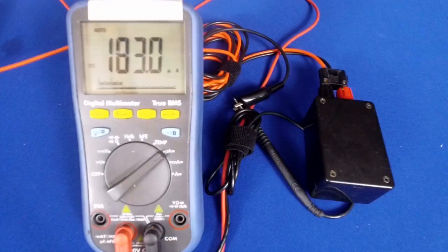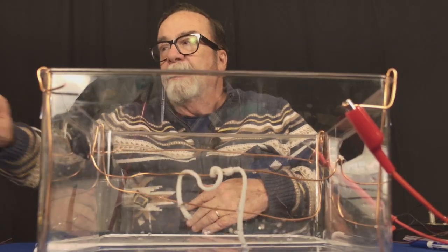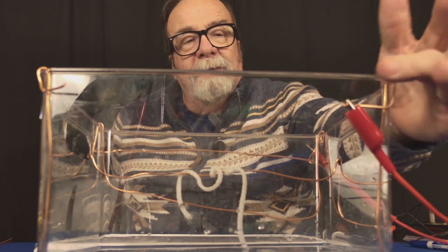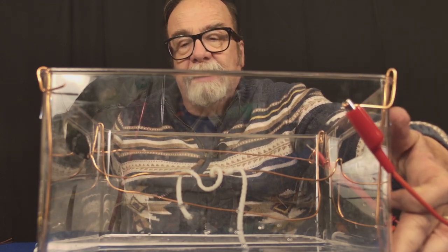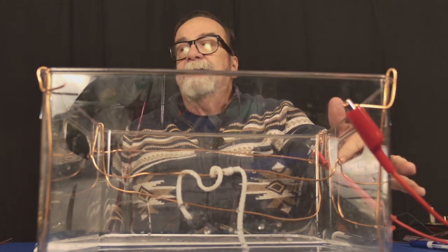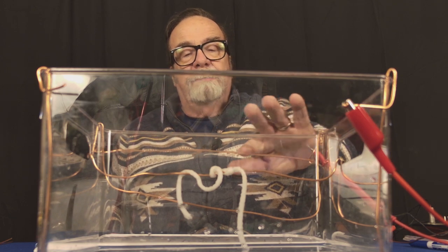is basically, here's my meter, and here's this little black box. Well, this little black box is a 24 volt, power limited to 100 milliamp power supply. And you'll notice that the negative of this battery is sitting on the negative of the meter. The positive of the battery is going over to a test tank right here to this wire, which is going down and it's underneath the water. The positive of the meter is sitting on what would be your cable.